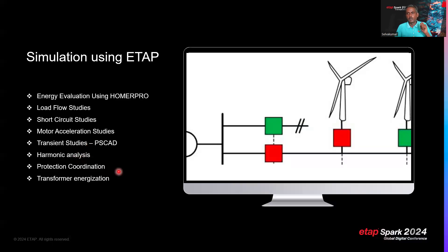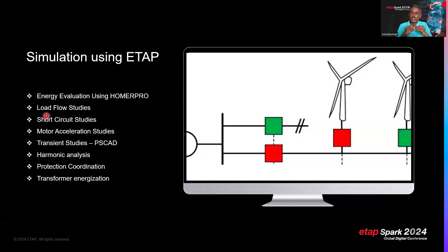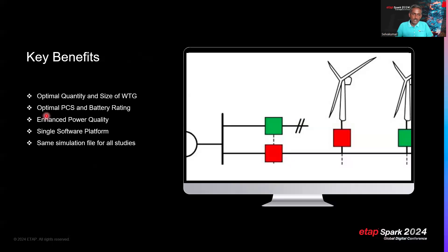Harmonic analysis and protection coordination are also required. With a configuration such as 3×12 MW wind turbine generators, a step-up transformer of at least 45 MVA is needed to step up from 33 or 35 kV to 66 kV. Such equipment sizing also needs to be validated. ETAP provides a single platform covering all these studies, with integration to PSCAD, to validate the complete technical feasibility of the system.